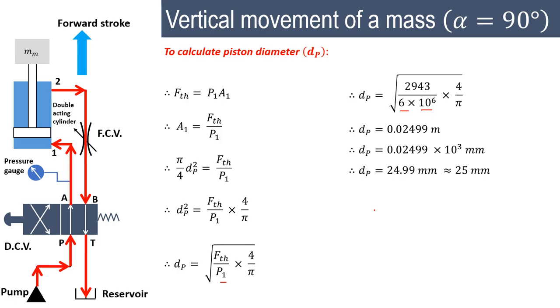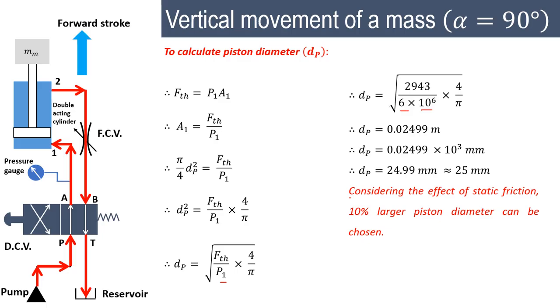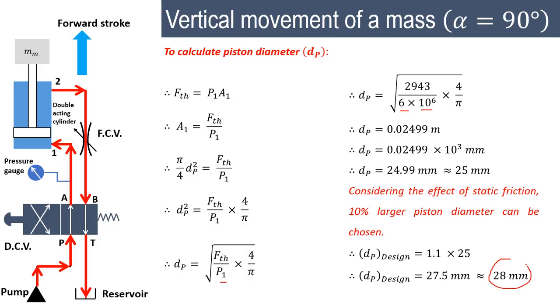Even though theoretically there are no frictional forces and we used only the limiting condition, we apply a factor of safety of 10%, so 10% larger piston diameter is chosen. The design diameter is 1.1 × 25 = 27.5 mm, which we round to 28 mm. This is the chosen cylinder diameter. During the return stroke, the weight comes down under gravity so there is no problem with the return stroke.